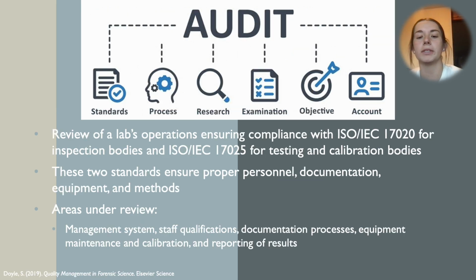When looking at an audit, it's a review of a lab's operations, ensuring compliance, usually with the standards ISO IEC 17020, which is for the inspection body part of the lab, and then the standard ISO IEC 17025, which is more for the testing and calibration bodies in the lab. These two standards ensure the proper personnel, documentation, equipment, and methods are being used within that lab. The main areas under review in an audit are the management system, the staff qualifications and their training, the documentation processes, the equipment, the maintenance of the equipment, and the calibration and reporting of results.